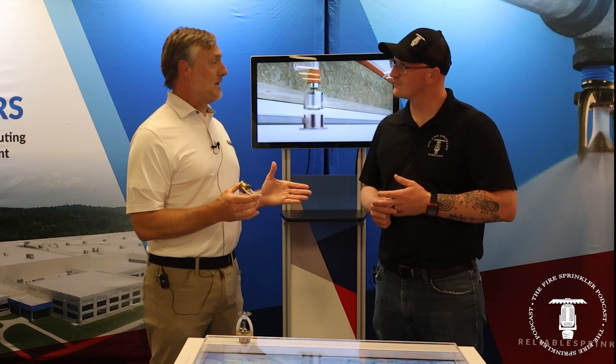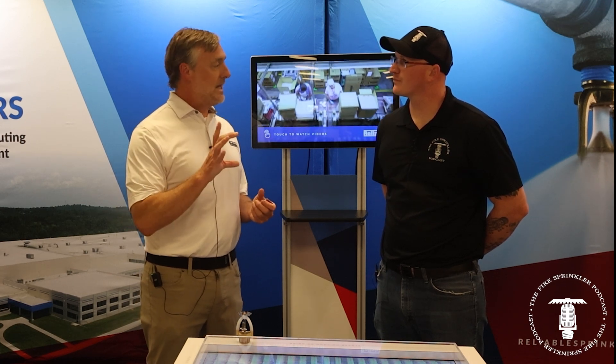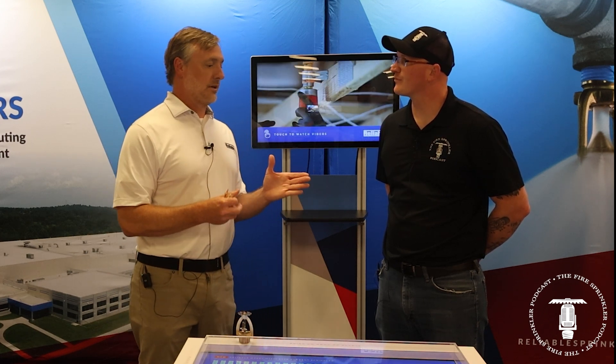If you find your way into a lithium ion battery manufacturing facility, the first thing you notice is they're massive — large, expensive projects. There are really two pieces to it: there's the assembly or creation of the cells, some people call it electrode cell assembly. And then there's a second piece — some people refer to as formation or aging — where they essentially condition the cells and bring them to life. When a lithium ion battery cell is first made, it doesn't have any stored energy. So they condition those cells, charge and discharge them, put them in higher temperature rooms, leave them for several days.